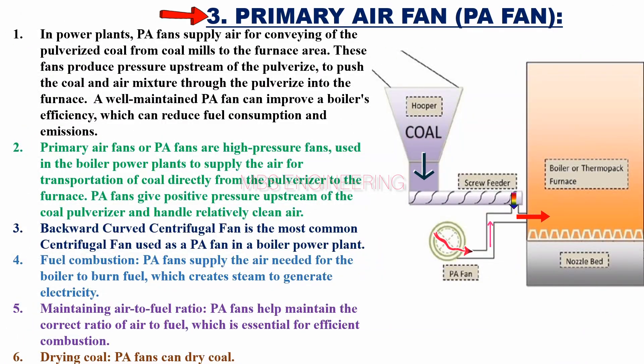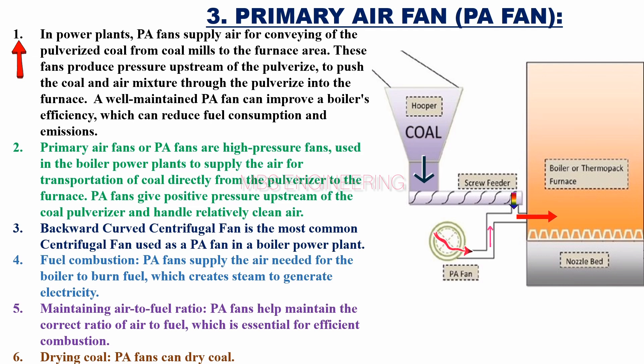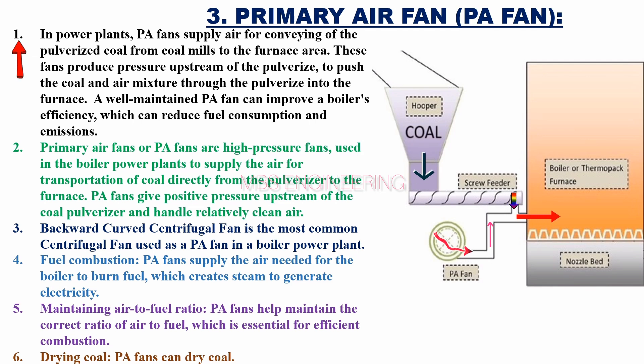Let's move on to the PA Fan. In power plants, PA fans supply air for conveying the pulverized coal from coal mills to the furnace area. These fans produce pressure upstream of the pulverizer to push the coal and air mixture through the pulverizer into the furnace. A well-maintained PA fan can improve a boiler's efficiency, which can reduce fuel consumption and emissions.